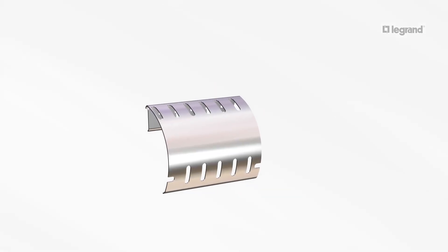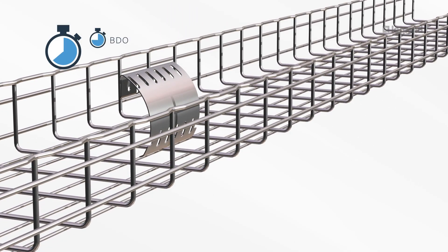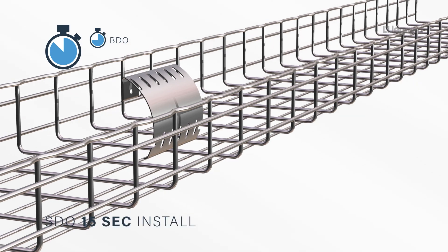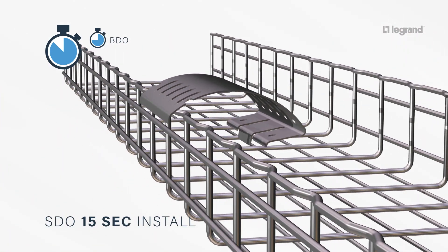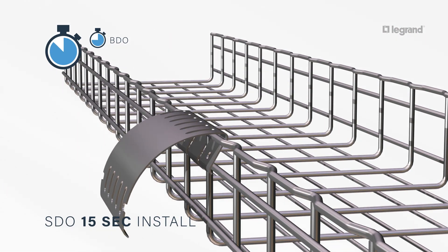SDO dropouts protect cables when exiting and entering the tray over the top of the tray. Slotted design allows for cable tie or Velcro tie wrap cable attachment. The 6-inch radius bend eases strain on cables and supports a larger capacity of cable.